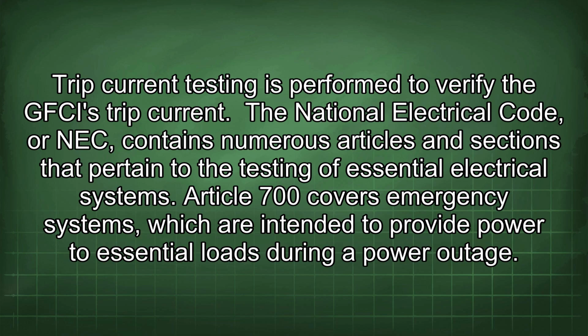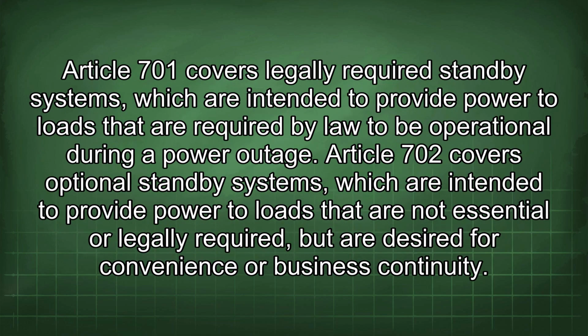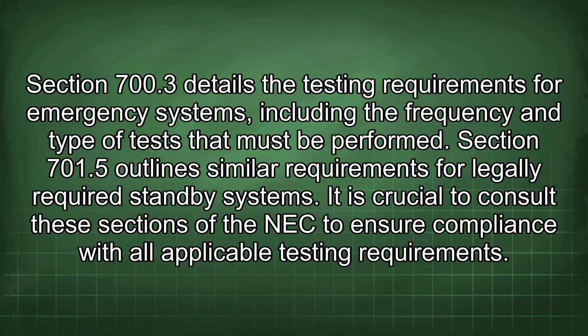The National Electrical Code, or NEC, contains numerous articles and sections that pertain to the testing of essential electrical systems. Article 700 covers emergency systems, which are intended to provide power to essential loads during a power outage. Article 701 covers legally required standby systems, which are intended to provide power to loads that are required by law to be operational during a power outage. Article 702 covers optional standby systems, which are intended to provide power to loads that are not essential or legally required, but are desired for convenience or business continuity. Section 700.3 details the testing requirements for emergency systems, including the frequency and type of tests that must be performed.